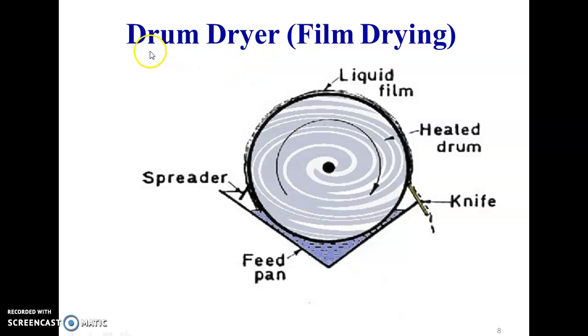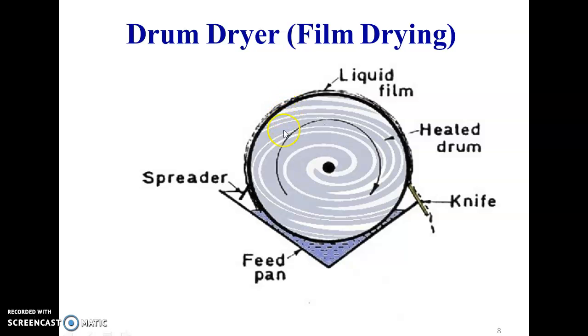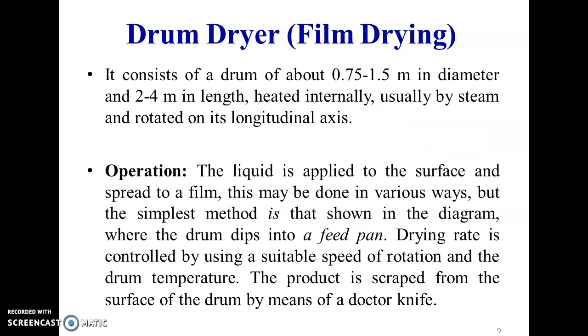The next one is the drum dryer, which is also known as a film dryer. It contains a heated drum by means of steam, and there is a pan provided in which the slurry is kept. This drum is slowly revolving, and while revolving, the drum picks up the slurry — that means some solid — from this pan. By means of a spreader, the thickness is maintained over this drum. While revolving, the moisture gets evaporated, and we get a dried product. This dried product is removed by means of a knife. So this is the drum dryer.